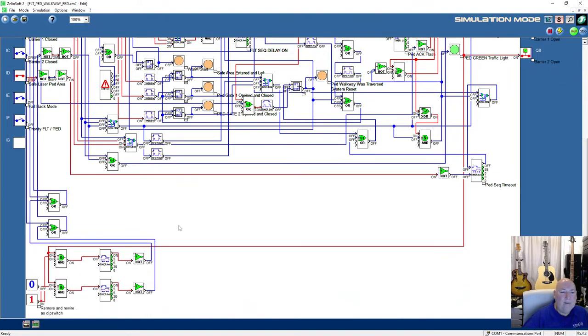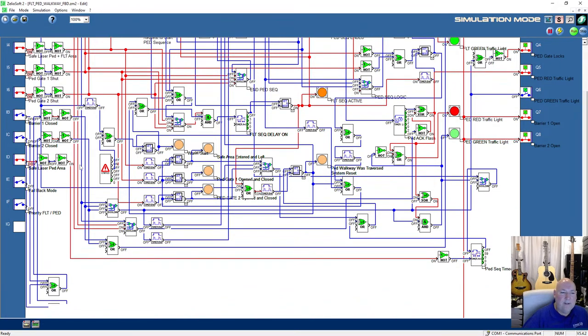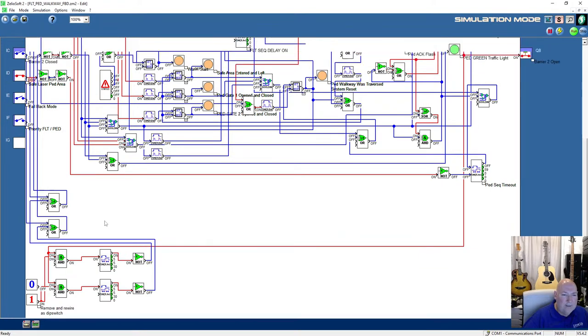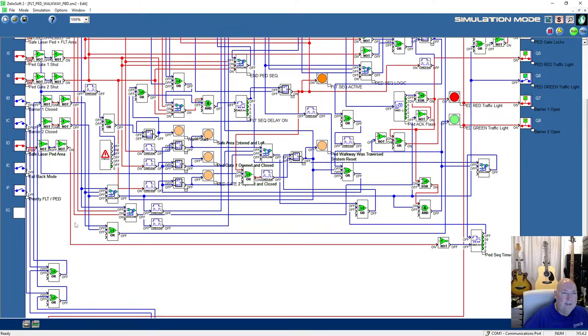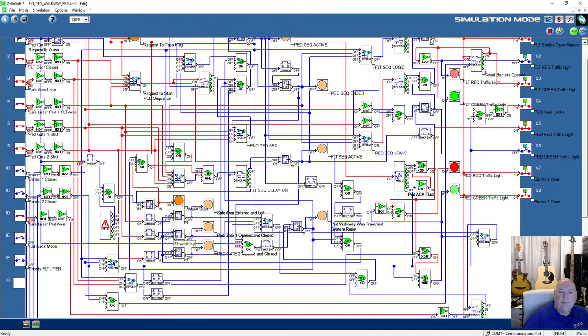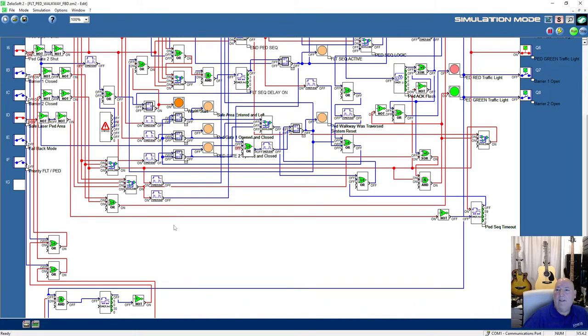Right, so what have we got going on here? Oh, we've got a green traffic light this time. We've got output there, barrier commands are open, output in, and we've got no signals on the close limit, which is what we'd expect, right? And our AND gates are sending through the signal. Okay, let's try a sequence. Request a crossing. So they've just dropped out and they're timing out. The barriers are closing. Yeah, so it did actually give you a delay, a simulated closing delay.